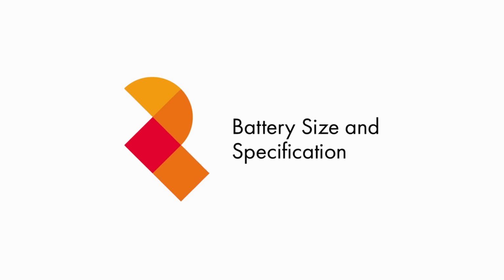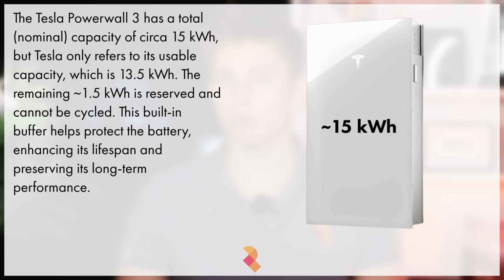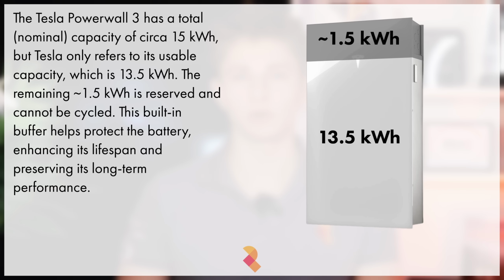To start with, Tesla Powerwall 3 is a 13.5 kilowatt hour battery system. It's only available in one size, 13.5 kilowatt hours. Now technically, the Powerwall 3 is a 15 kilowatt hour battery unit - that's its nominal capacity. However, for the purposes of keeping things simple, Tesla only talk about its usable capacity, which is 13.5 kilowatt hours. That 1.5 kilowatt hour, 10% storage margin that can't be cycled is one of the reasons that the Powerwall 3 has such a great industry-leading warranty, which I'll come on to later.